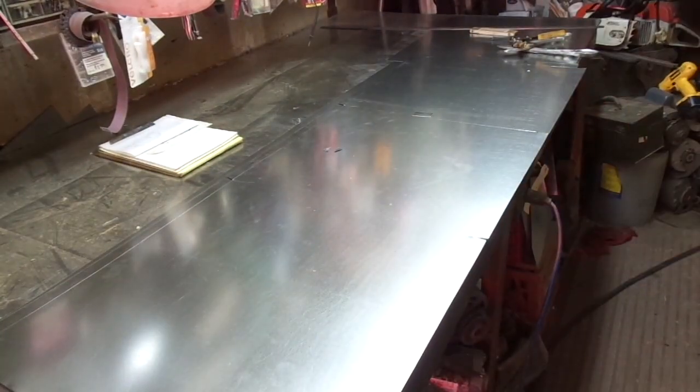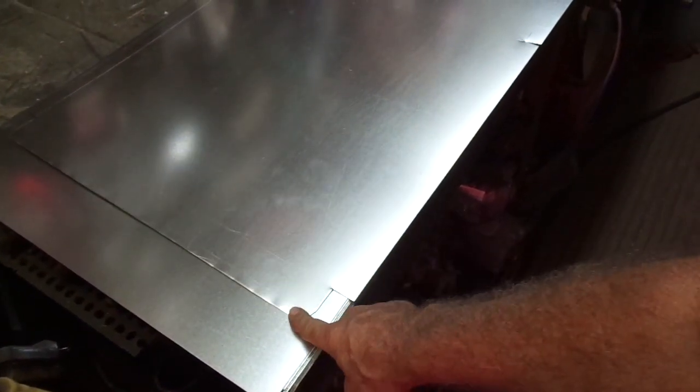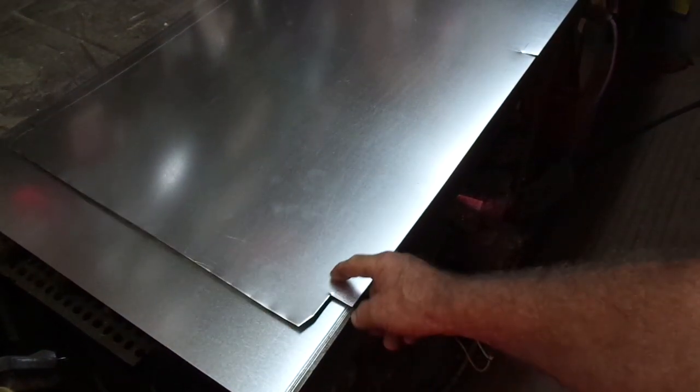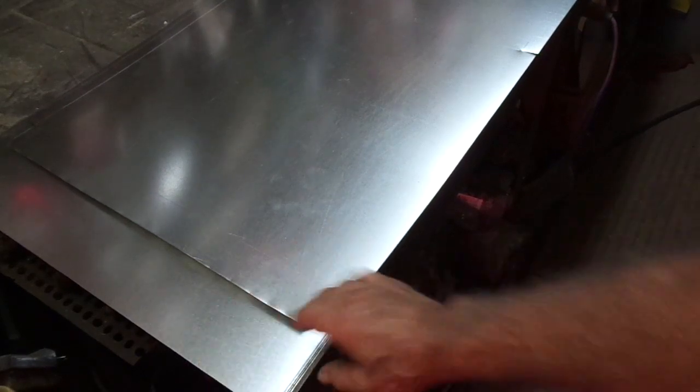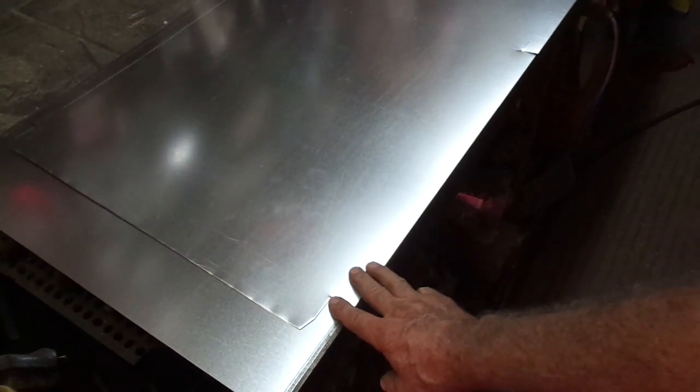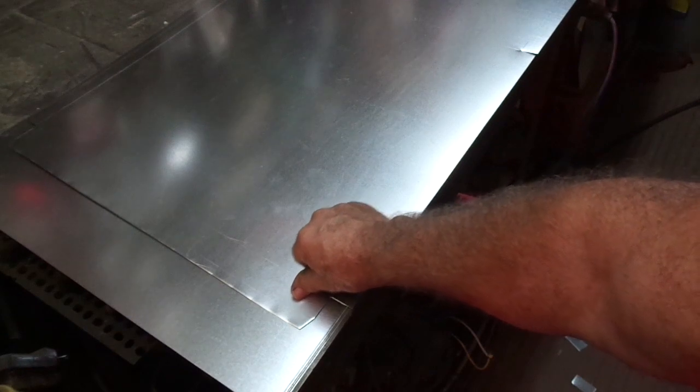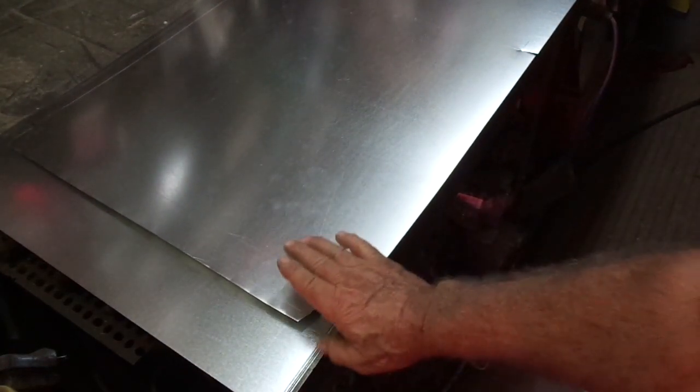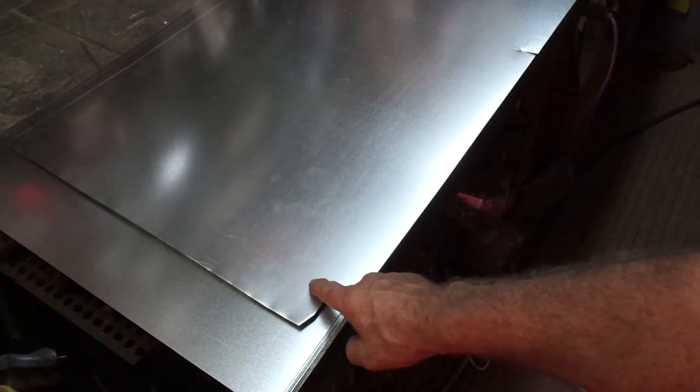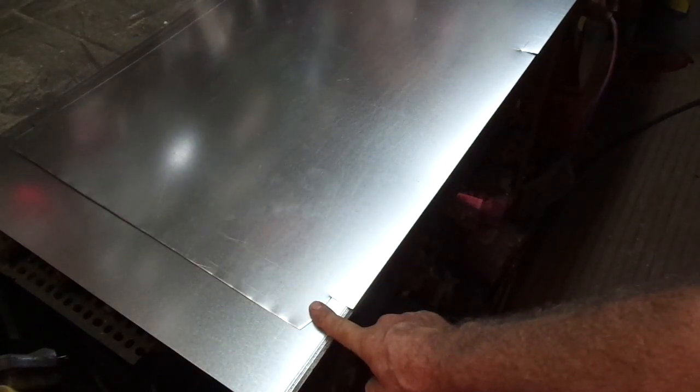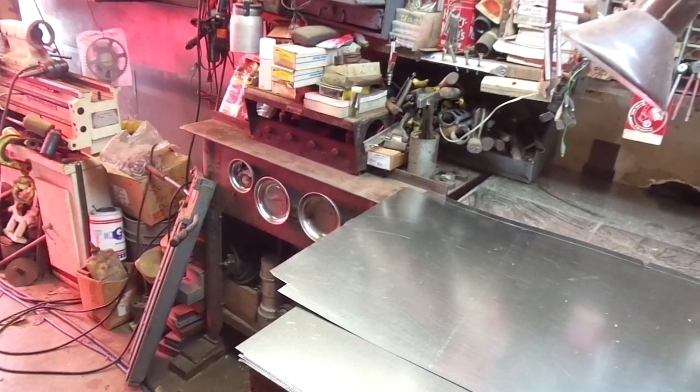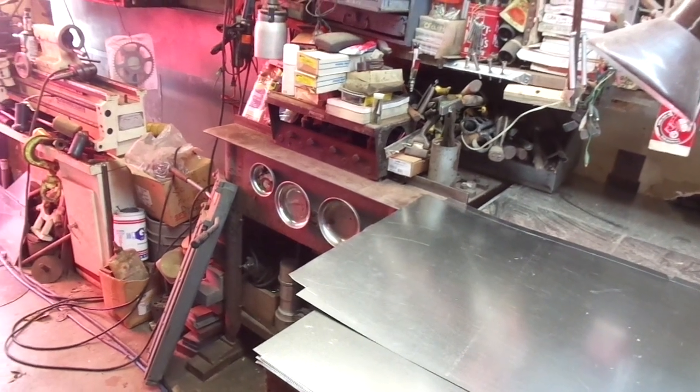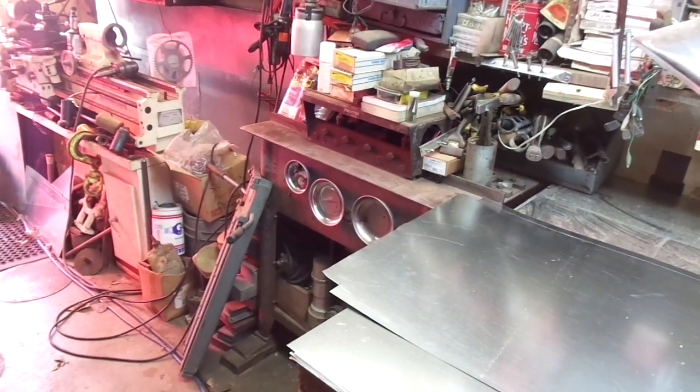It's always a little awkward working around a camera. Now, what we'll do is right here where this 90-degree reinforcement is going to fold over, we're going to have an additional reinforcement by folding that over to about a 45 and then a 90. And then the other side pieces are going to be nailed into the side of this lock former joint here, this Pittsburgh lock. And so what I think I'm going to do now is cut off of this mark and notch another inch and an inch and a half, which is the depth of the reinforcement that's going to come in from the side.